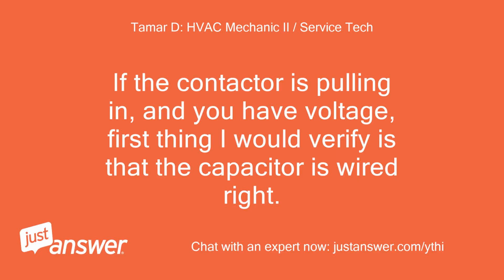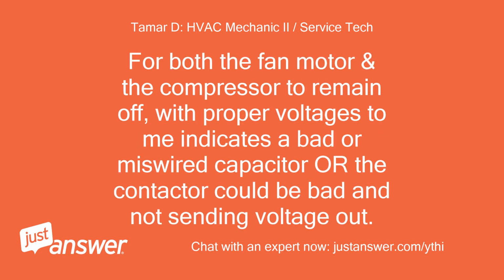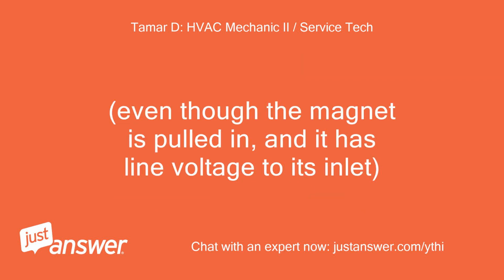If the contactor is pulling in, and you have voltage, first thing I would verify is that the capacitor is wired right. For both the fan motor and the compressor to remain off, with proper voltages, to me indicates a bad or miswired capacitor, or the contactor could be bad and not sending voltage out, even though the magnet is pulled in and it has line voltage to its inlet.